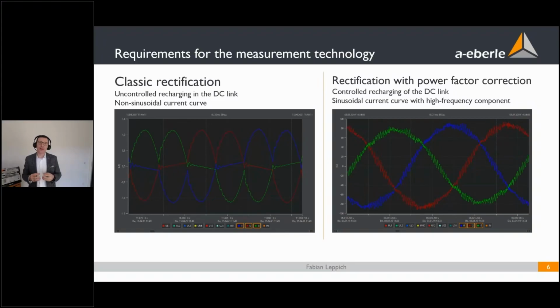At this time we have a non-sinusoidal current curve. The current will influence the voltage, and by which factor? By the impedance. The impedance is very low in the high voltage grid, a bit higher in the medium voltage grid, and in the low voltage grid, at the transformer station, it is the highest one you can have. Therefore it's clear that a non-sinusoidal current curve will always influence the voltage, especially deep in the grid.